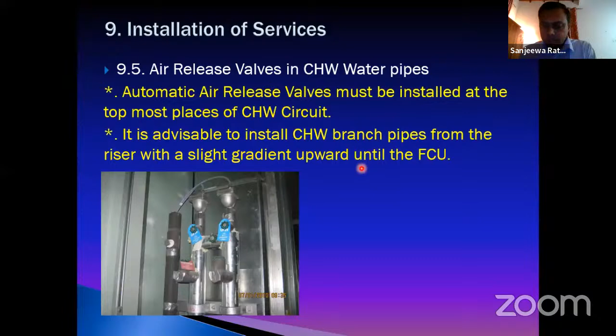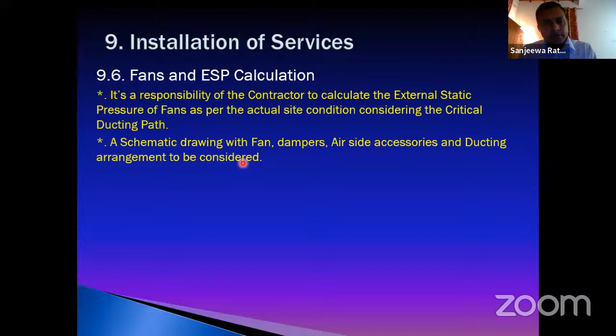Then, as we did with the pumps, fans also need to be considered. Even though the consultants designed and sized the fan, with size constraints the duct path may be changed. So it is also the contractor's responsibility to calculate the external static pressure of the fan as per the actual site situation, and to consider the critical path. With a proper schematic drawing of all the components of the system, it must be done. Here is an example of how to calculate the external static pressure of the fan, from our practical experience.